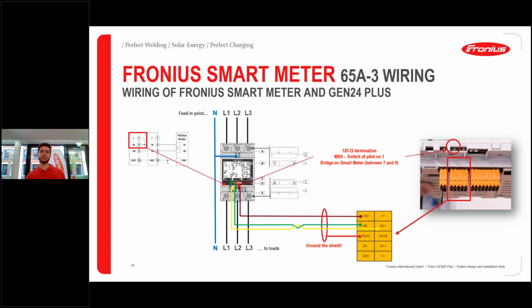So this answers the question where we have to install it. Now the question how. And I've also mentioned that data communication is the most important thing, and we can see it here in these colors: brown, green, and yellow. That's just my visualization to separate them. So we have a 3-pole line coming from the smart meter to the inverter. This is our connection, and it's a Modbus RTU connection, RS485 data communication.